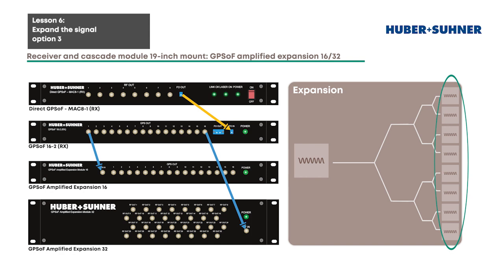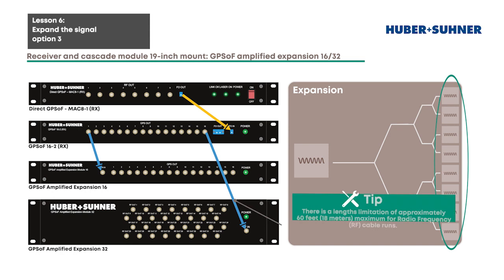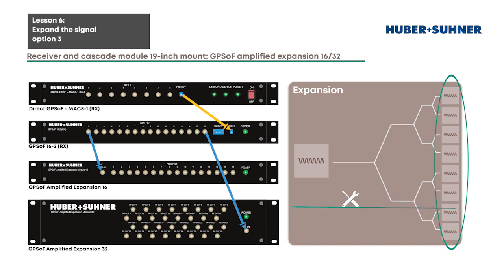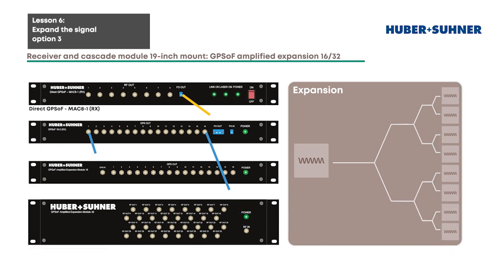The 16 and 32 port modules can be used in combination with all RF out ports in the GPS-over-Fiber portfolio, but keep in mind the length limitation of a high-quality RF cable, which is approximately 60 feet or 18 meters. Don't forget to factor in the cable length that is used to connect the extension modules. For a valid length estimation, please contact your system architect or HUBER and SUHNER technical support.